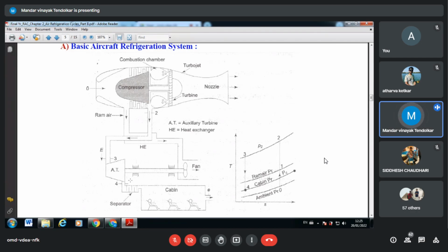Then there is a moisture separator, so anything not meant to be exposed to the cabin gets out from here. Finally the cool, cold air gets passed through the cabin, and naturally it absorbs the refrigeration load and comes to point E. So this 4 to E is my refrigeration load: compressor, heat rejection, expansion, evaporator.